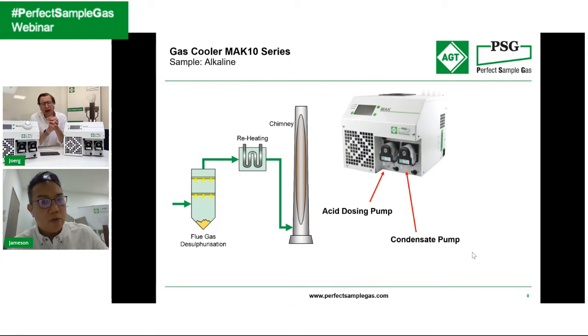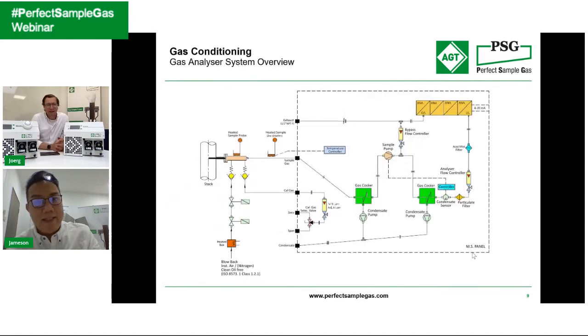Yes, exactly. We can inject phosphoric acid into the inlet of the sample before it's introduced into the exchanger. So the second peristaltic pump becomes a condensate pump - it looks alike, but the speed we use is different.